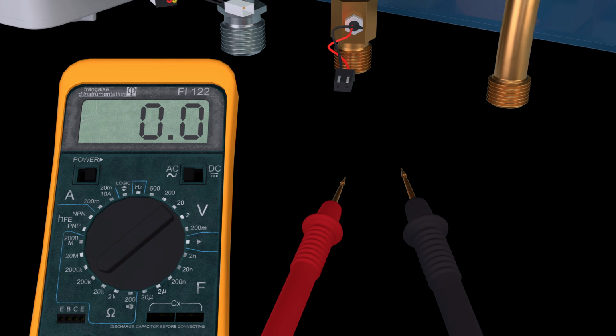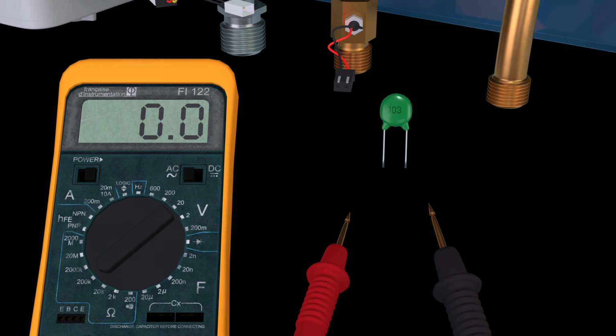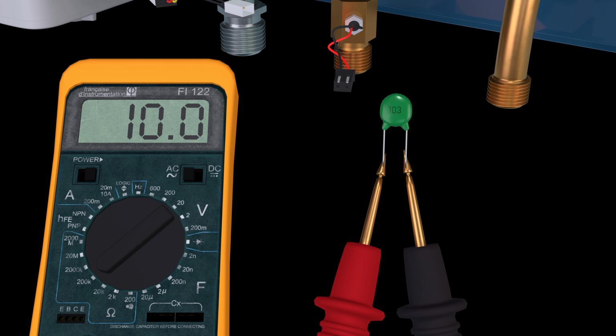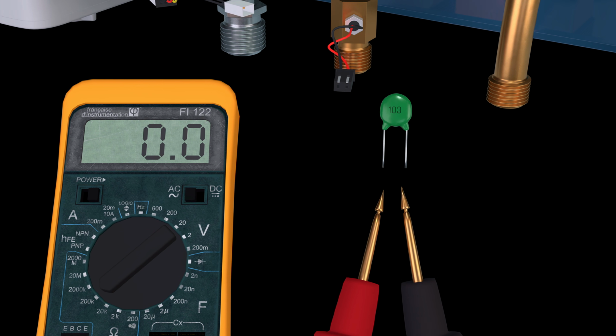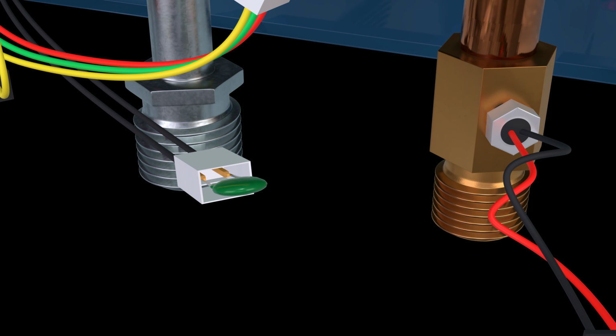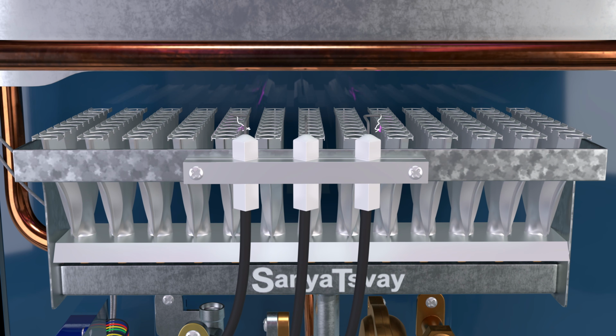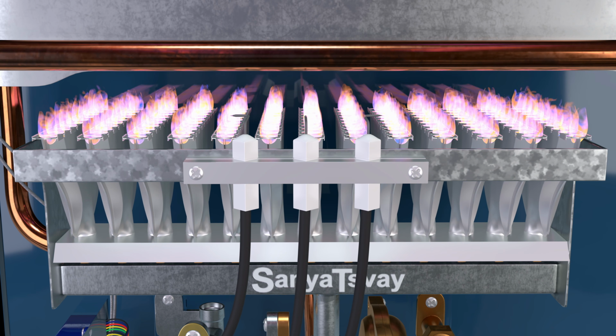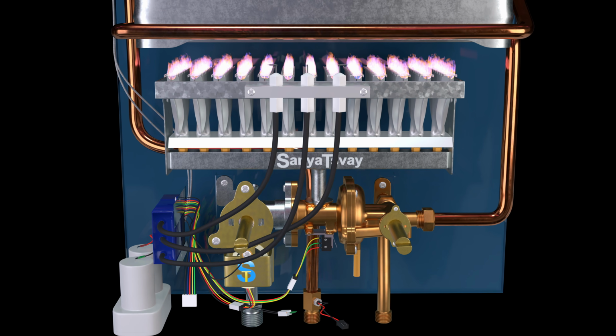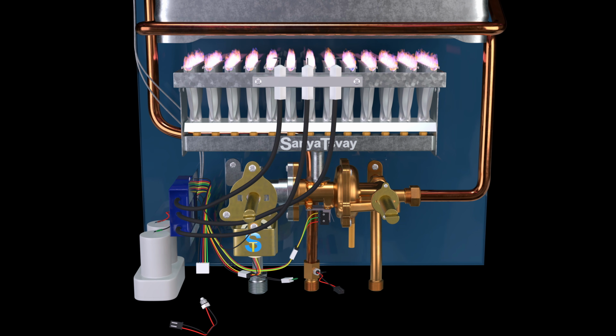So I decided to take an alternative approach. I installed a 10 kilo ohm resistor instead, and the heater immediately came back to life. So it's possible that the new sensor had a different coefficient or simply wasn't compatible. This is essentially a kind of bypass that imitates the signal of a working sensor. Using this method, you can confirm or rule out that the problem is indeed the temperature sensor. Please note that operating a gas water heater this way is dangerous, so I emphasize that only original spare parts should be used.